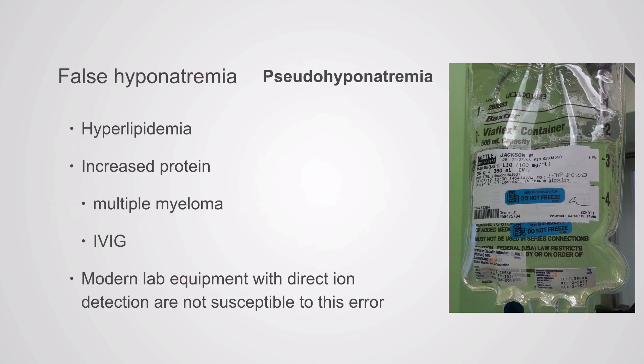We see pseudohyponatremia with increased lipids — hyperlipidemia — and increased proteins, usually immunoglobulins. You'll see this in multiple myeloma, Waldenström's macroglobulinemia, or with IVIG (intravenous immunoglobulin) therapy. Not every lab instrument is susceptible to this error; equipment using direct ion detection is not affected. You can call your pathologist to find out which method they use, or simply order a serum osmolality — if it's low, you have true hyponatremia; if it's normal or high, you have false hyponatremia.